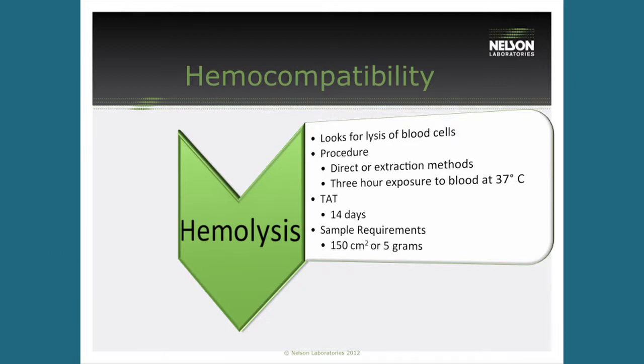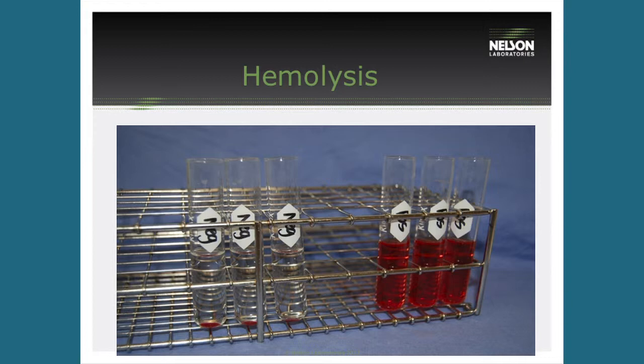By evaluating both the physical properties and the extraction, we can look at both sides of hemolysis. We take the device, put it in contact with blood cells, and look at how those blood cells interact with your device. This right here is an example of our positive and negative controls. On the left side is our negative, which is polypropylene, and on the right is our positive, which is a nitrile glove.